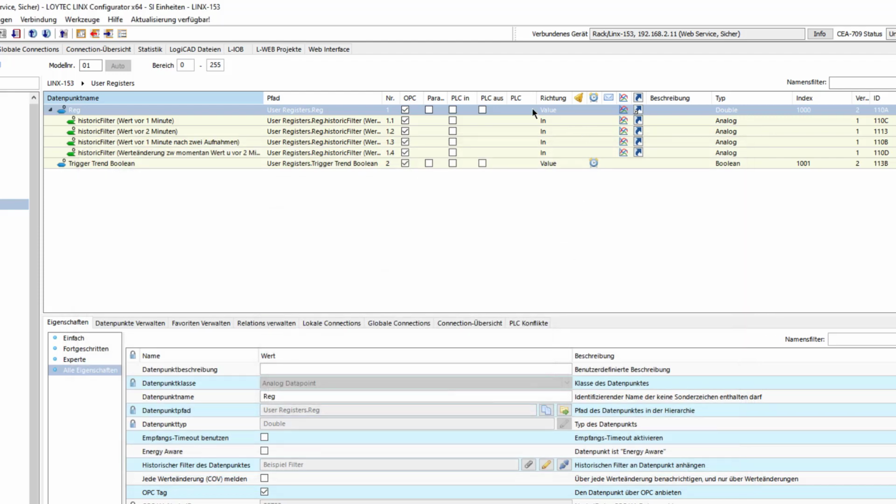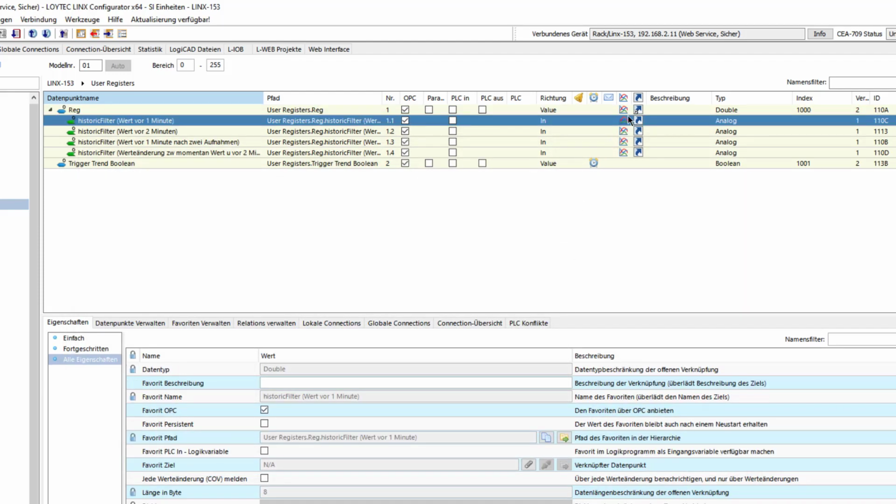Should you want to automatically calculate a value difference to a current value, for example, every 2 minutes, you could capture the value 2 minutes ago and subtract it from the current value using the subtract from column. This functionality can be used to automatically calculate energy consumption over a specified period, in this example 2 minutes, but could be extended over days, weeks, and so forth.